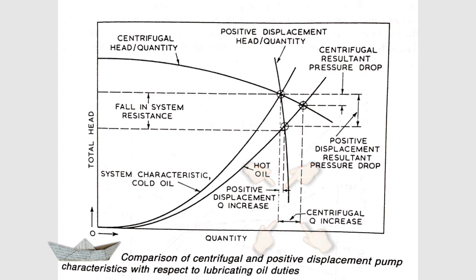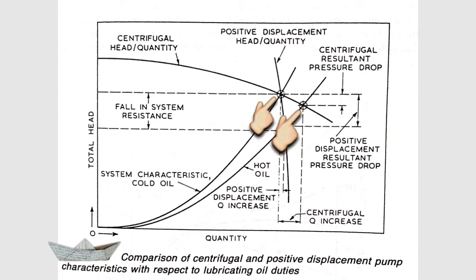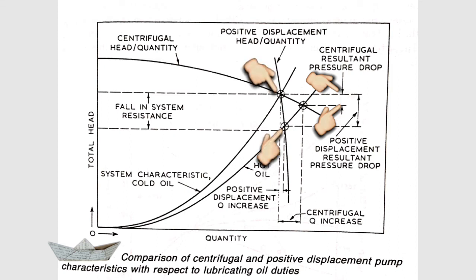Now analyzing the pressure head: as the oil becomes hotter, the pressure keeps dropping for the centrifugal pump, but this drop is relatively moderate. For the positive displacement pump, the pressure drop is immense — roughly double that of the centrifugal pump, for comparison purposes. So here also the centrifugal pump has the upper hand. As lube oil becomes hotter, the pressure drop in the centrifugal pump is less than in the positive displacement pump, which is why centrifugal pumps are more preferred for lube oil duties.